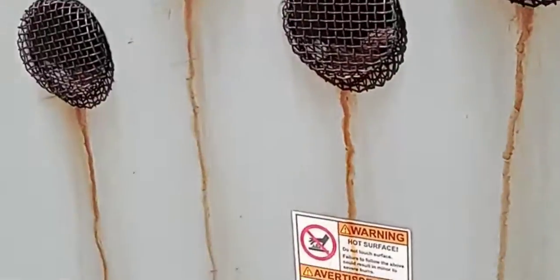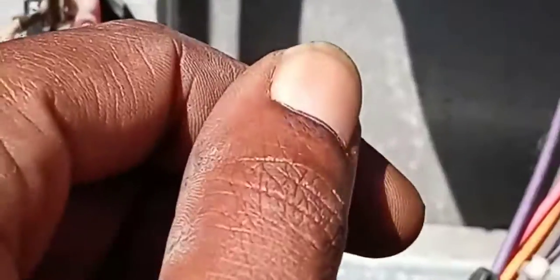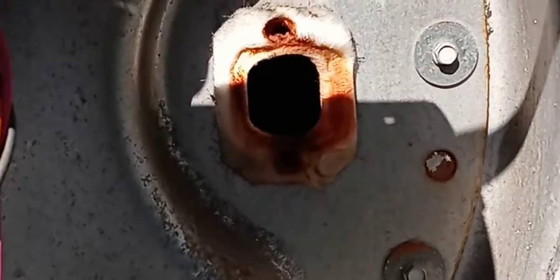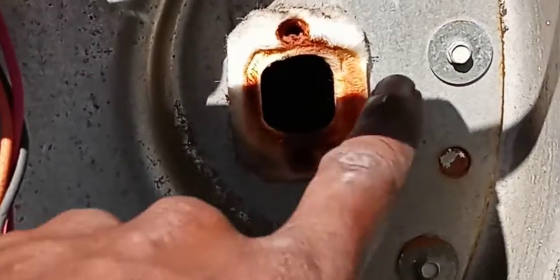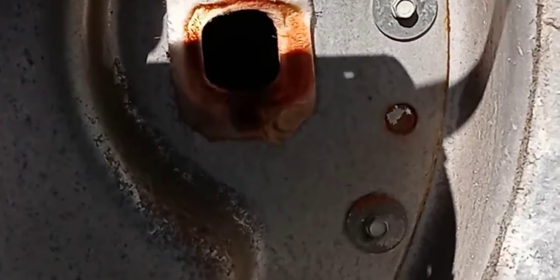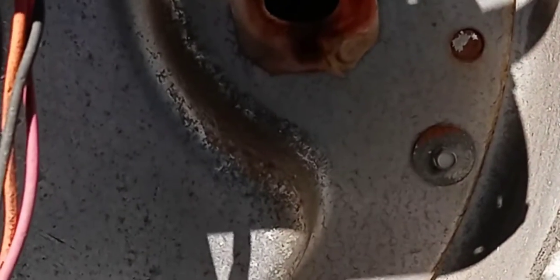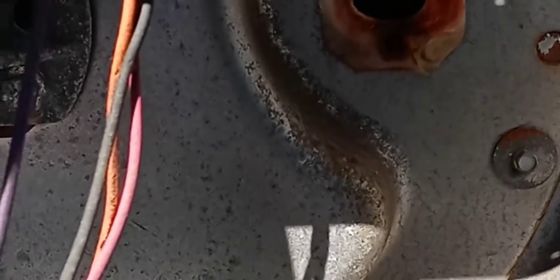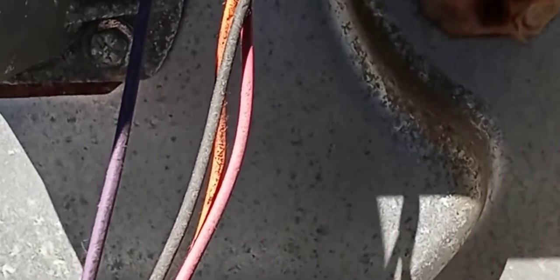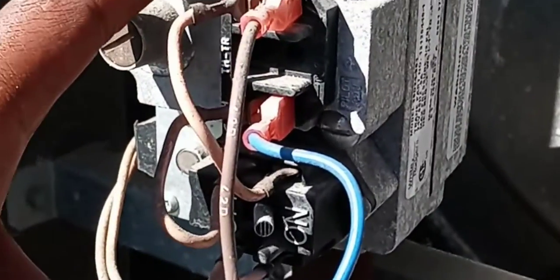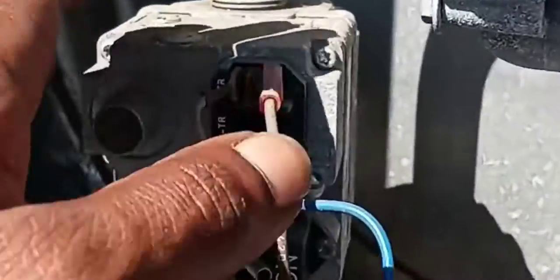As I'm investigating, before I took the hot surface igniter off, because a lot of times those screws are breaking there. These screws break because they're so rusty from the heat and the moisture. It'll just rust the screw out. And that becomes a whole new headache, trust me, because then you got to drill a new hole and all this nonsense. But the igniter still got to be in the correct position so it could catch the gas that's coming out. So anyway, before I took the screws out of there, I verified this was working.